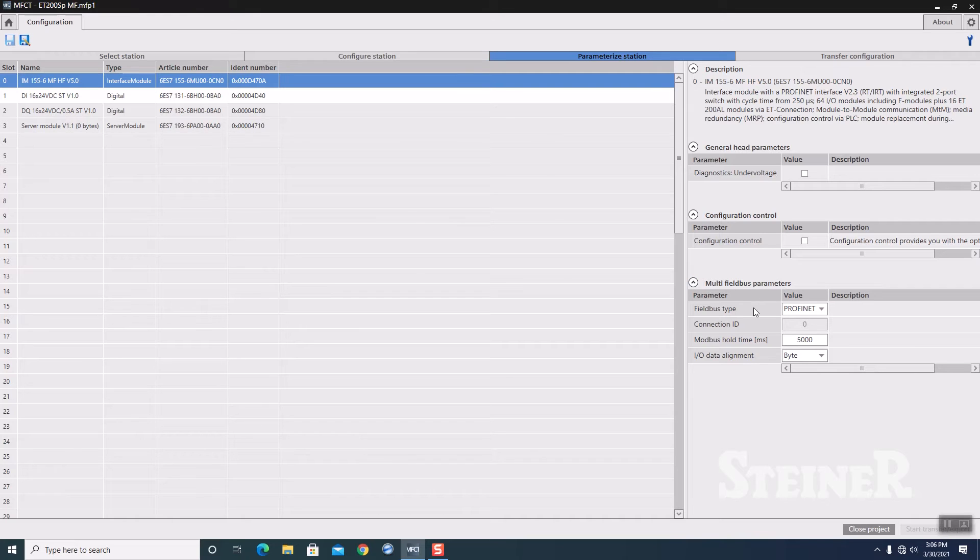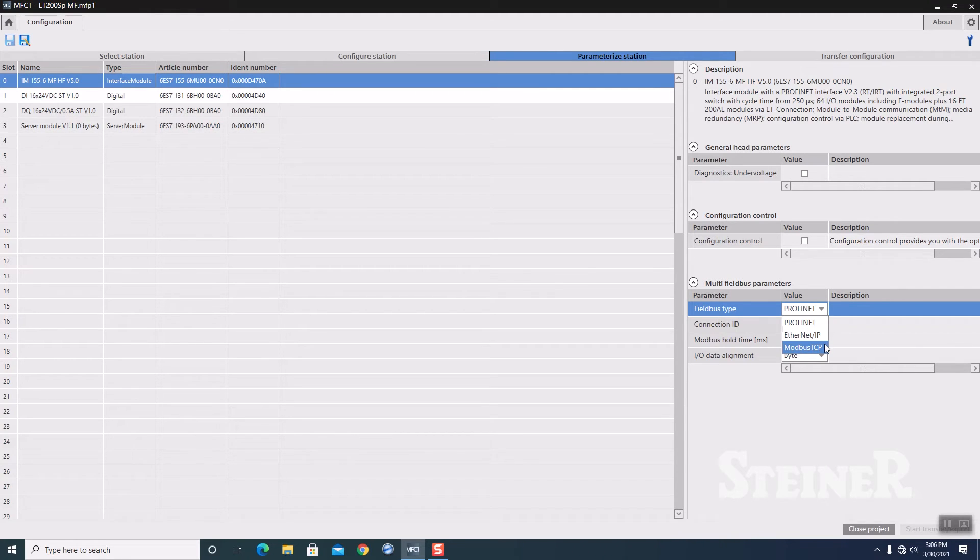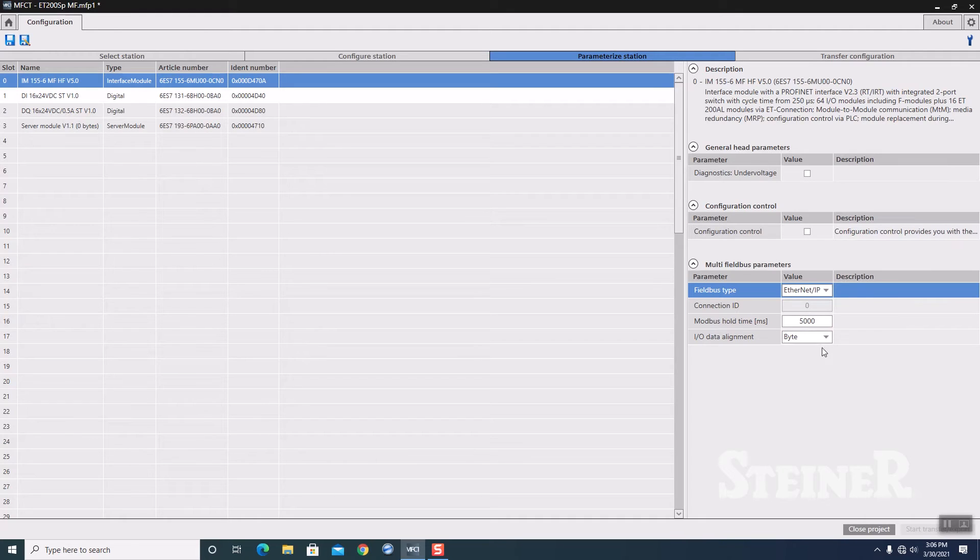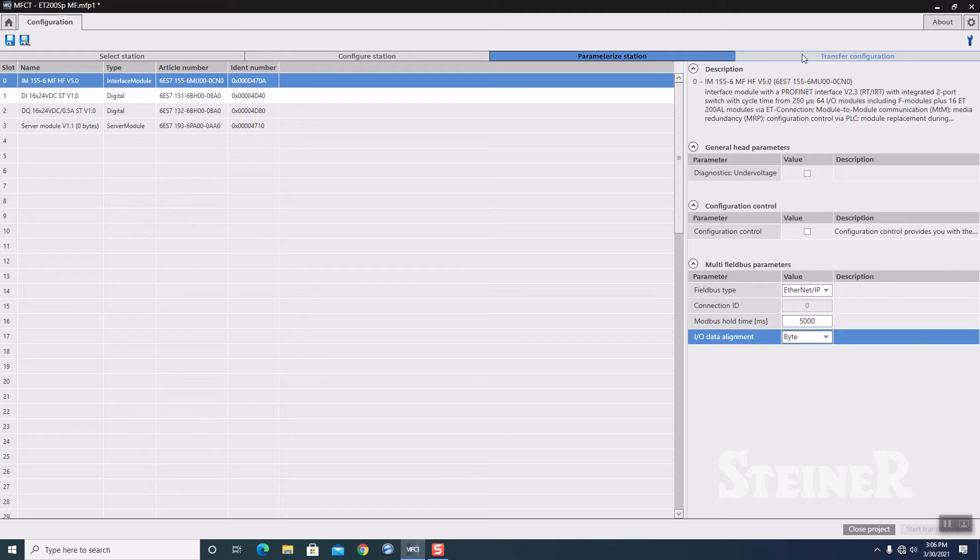Then our multi-field bus parameters. We're going to go to our field bus type. It defaults to PROFINET. Hit the dropdown. You see you have PROFINET, Ethernet IP, or Modbus TCP. We're going to do Ethernet IP today. And our I/O data alignment, you have the selection for byte or word. We're going to leave it at byte.